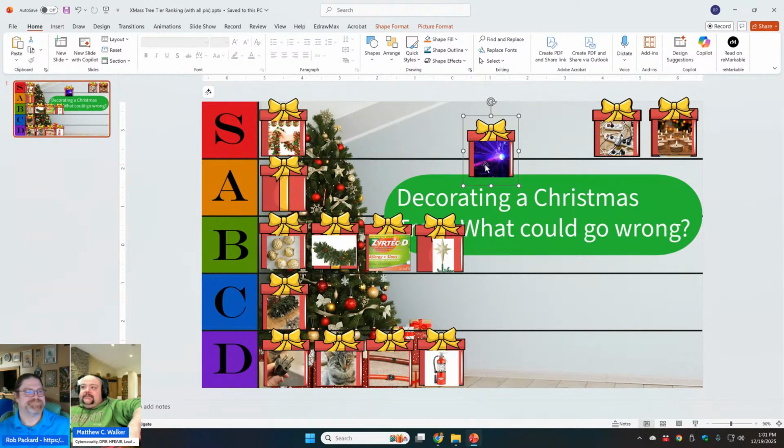However, seizure activity has led to fatal events before. So looking at a use-related risk analysis, one of the things we aren't allowed to take into consideration is the probability of occurrence. So when we're tracing this out, we've got to assume the absolute worst case scenario happens every single time, regardless. Yep. So 100% everybody that walks by my Christmas tree has seizures instantly.